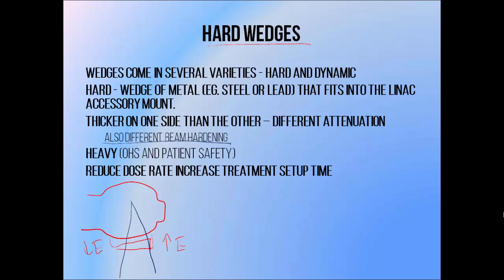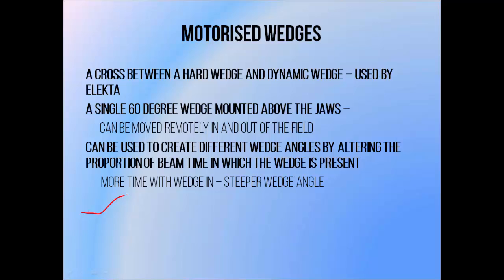These days we don't have to use hard wedges, although they are the most straightforward approach. We can also make use of dynamic wedges, which produce angled dose distributions via moving a filter through the beam. In order to keep setup time and OHS risks to a minimum, it's desirable to use a wedge that you can control from outside of the room. The two major linac manufacturers, Elekta and Varian, take different approaches to remotely controlling beam wedging.